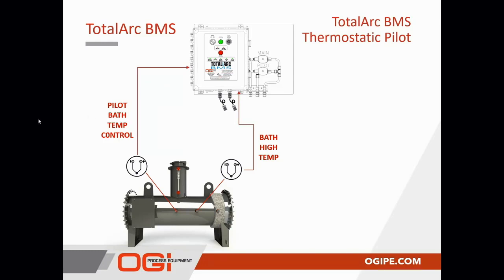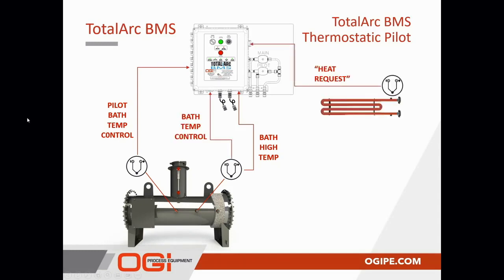After the pilot is lit in this condition, where the bath is cool enough and the safeties are met, the main burner will cycle on and off depending on the process or bath electronic temperature controllers, which define the call for heat condition. The pilot will remain on as long as the heater safeties are okay and the pilot bath temperature controller set point is not exceeded. Again, the control configuration is focused on smaller heaters, as we've discussed in the previous version. And note that if the pilot is lost, the BMS will shut down the main burner and the pilot, and the BMS will perform a 5-minute post purge and attempt to relight the pilot.